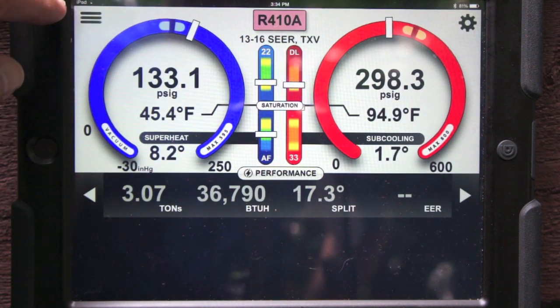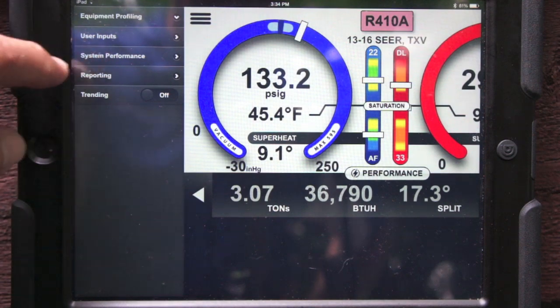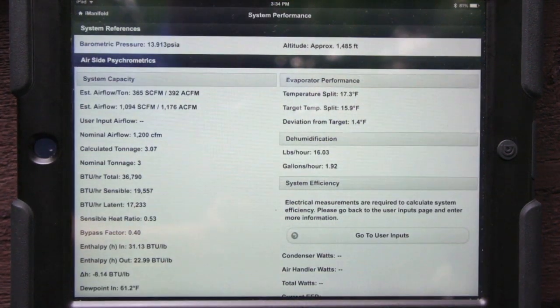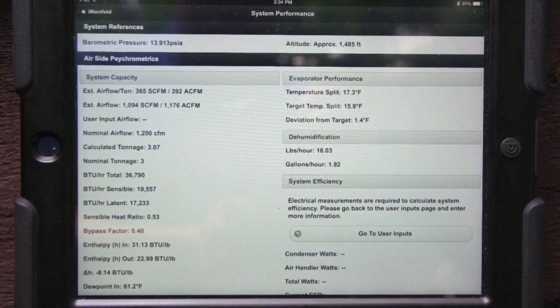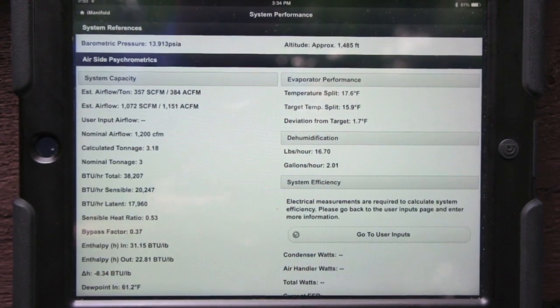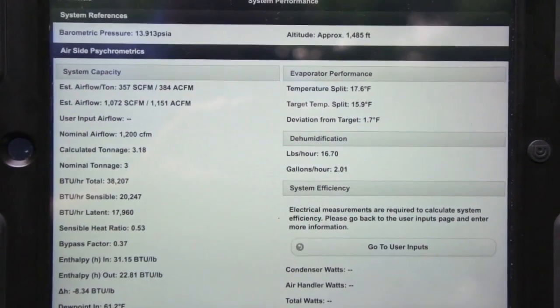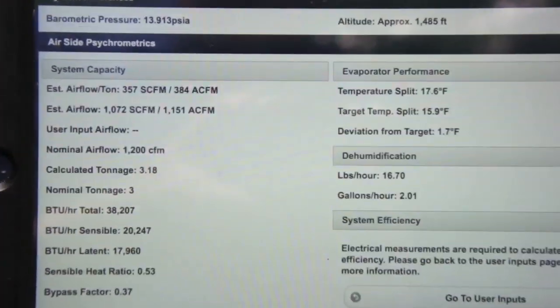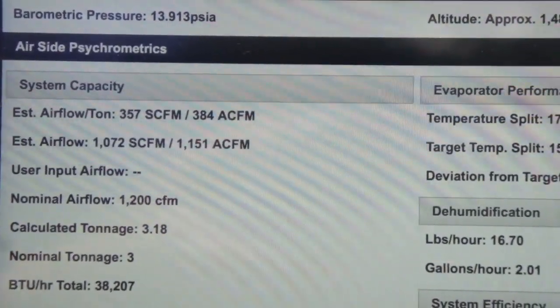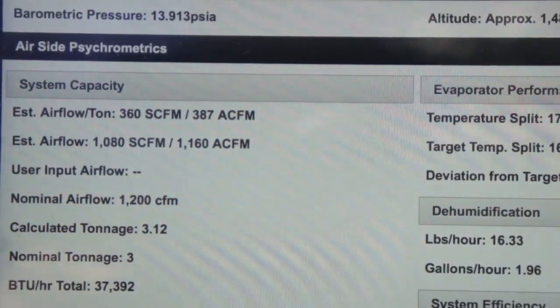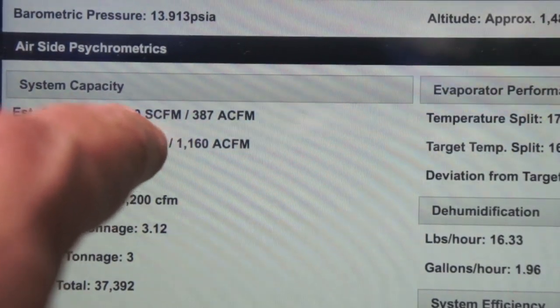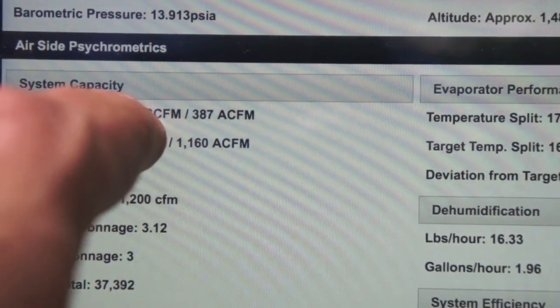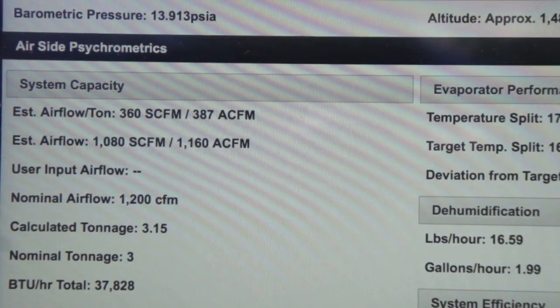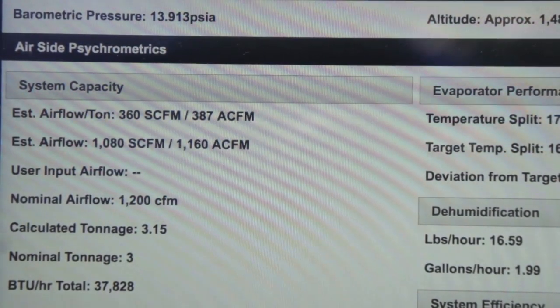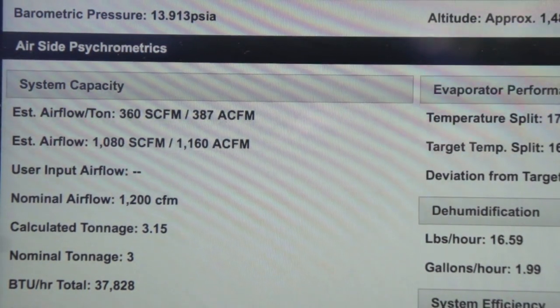And that's because if we go up here now into our system performance, the airflow is being calculated in real time. So what we're looking at here, I'm going to zoom in just a little bit so you can see this. It's still probably got to settle out a little bit here, but we're moving an estimated airflow of 360 standard CFM per ton, 387 actual, 1080 standard CFM total airflow, and 1160 actual.